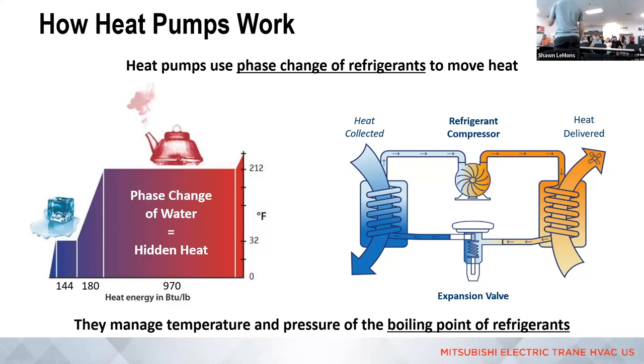So all we're really doing is applying that phase change to the refrigerants. We're not working with water anymore, we're working with refrigerants, moving them around in that cycle. We're compressing it to add a little extra. On the blue side, we're dropping that refrigerant below the outdoor temperature - if it's 0 degrees outside, we'll drop the refrigerant down to maybe negative 10, some degrees lower than outdoor temperature. As it's lower than outdoor temperature, it absorbs heat out of that air, and that heat moves into the refrigerant and changes its phase. So it's not just 1 degree we're capturing, it's hundreds of degrees - not quite as good as water, but hundreds of BTUs we're absorbing into that refrigerant.